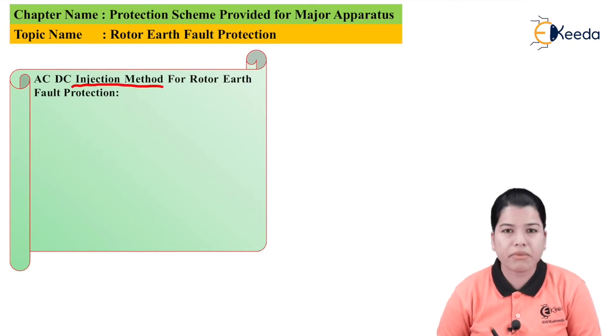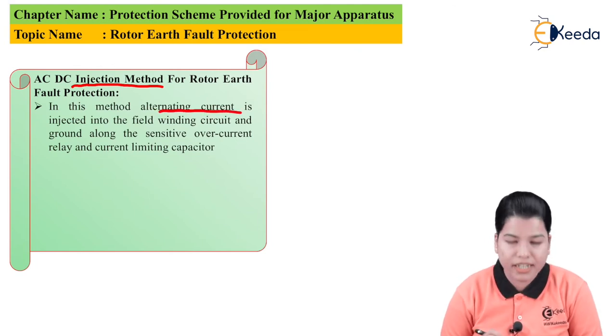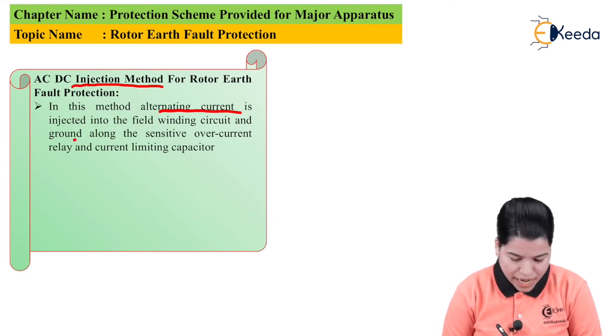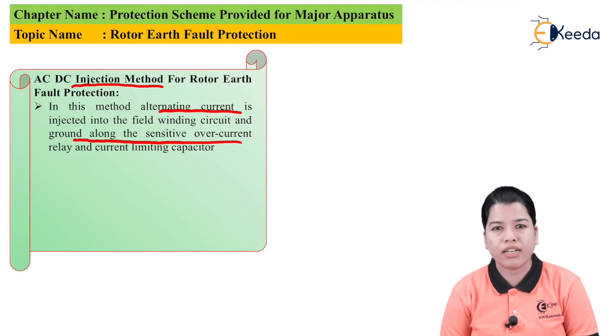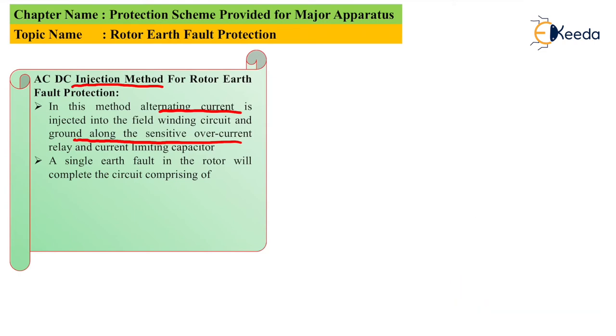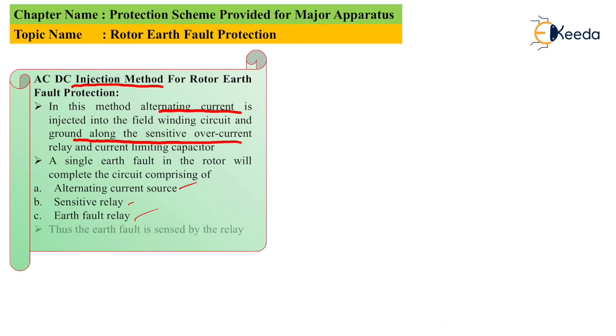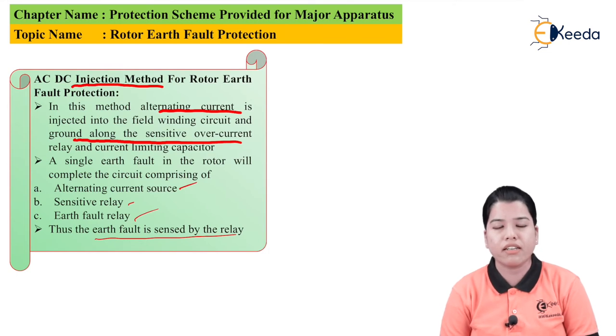The second method is the AC injection method for rotor earth fault protection. As the name suggests, in this method, alternating current is injected into the field winding and the ground circuit along with a sensitive earth fault relay. A current limiting capacitor is also connected. A single earth fault occurring in the rotor will complete its path through a circuit comprising the alternating current source, sensitive relay, and earth fault relay. Whenever the fault occurs, it will be sensed by the relay, which will signal the circuit breaker to isolate the faulty part from the healthy part.